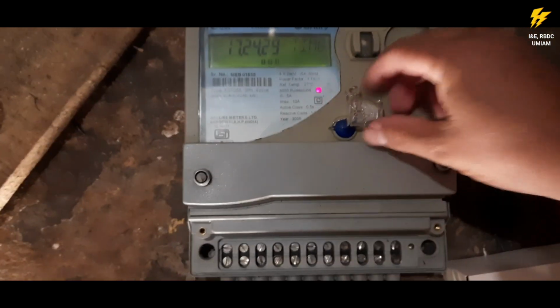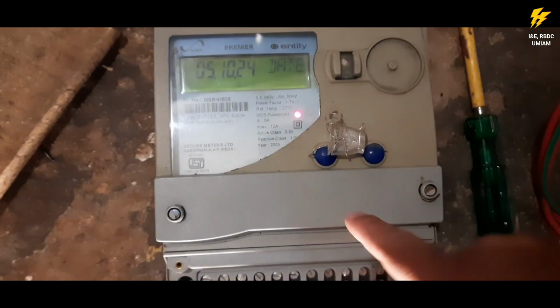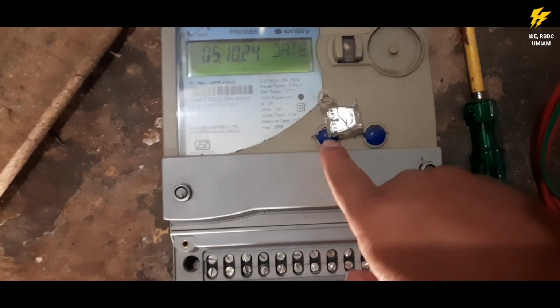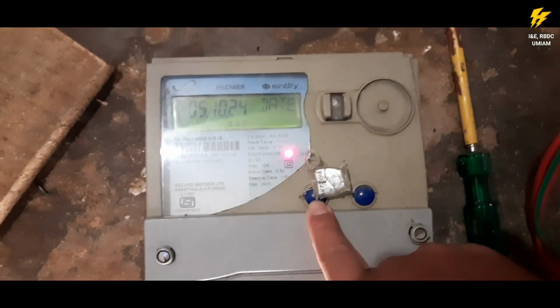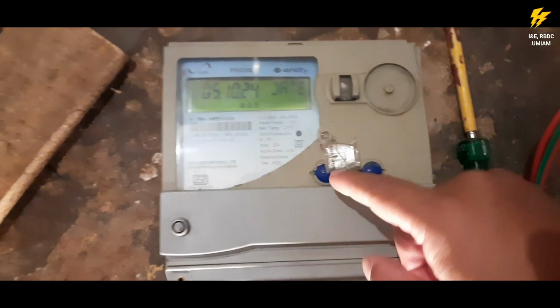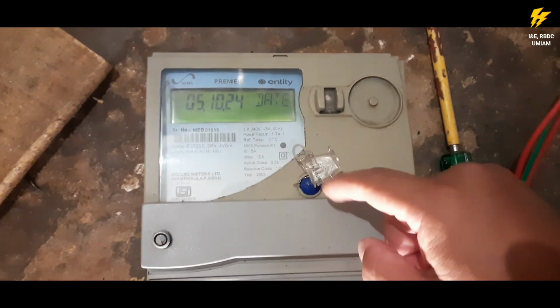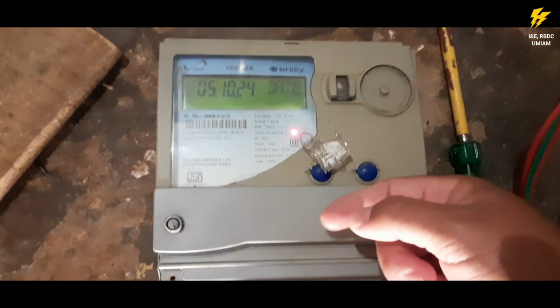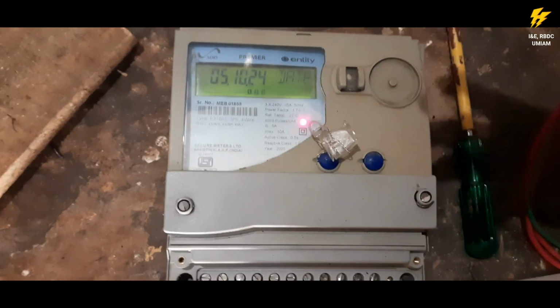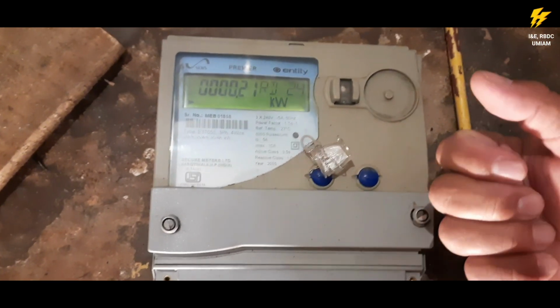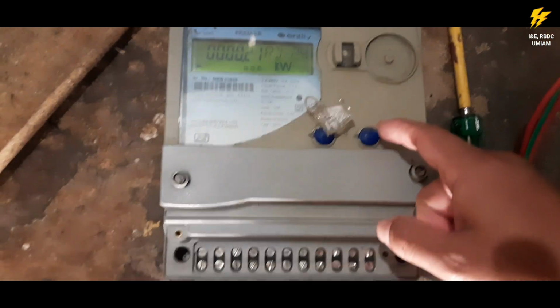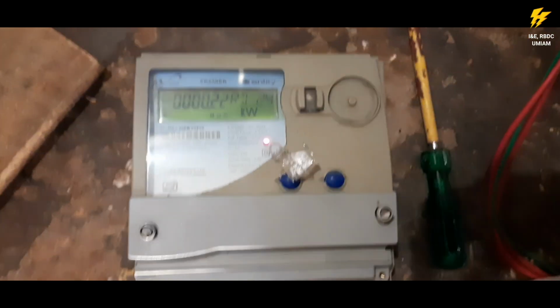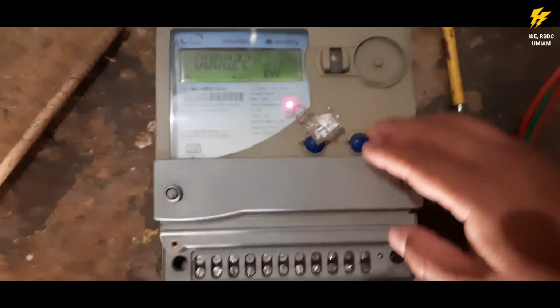You see this, the first push button is actually for maximum demand, for resetting. So I have deactivated it by putting a seal here, so that you cannot reset the maximum demand. Only the utility or the authorized personnel is allowed to reset this. I will show you that also later, but we will first see the readings.